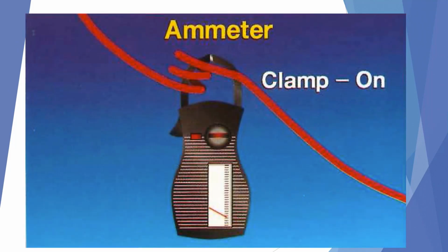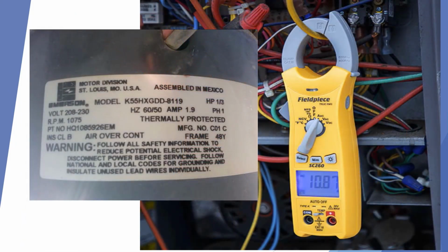With an amp meter, which is a clamp-on type meter, we can read the amp draw to a motor or a device on the system to make sure that it's drawing the proper current designed for that system and for that device. All motors and components that draw current in a system will have an amp draw listed on it as to the current amp draw that should be for that device. Checking with an amp meter to make sure that the motor is running within its design parameters is a part of troubleshooting the system.